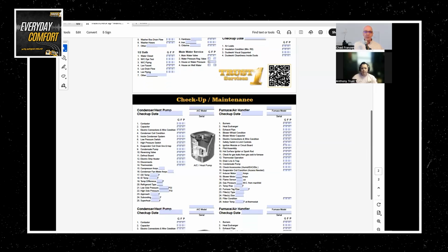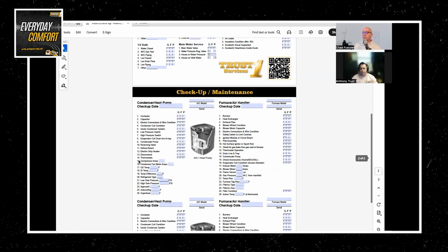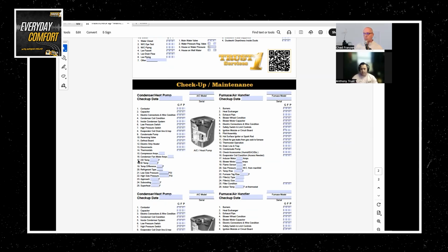You're checking capacitors, contactors, coils, refrigerant pressures, subcooling, superheat. Why is this level of detail important? Yeah. So like I said earlier in this episode, capacitors are basically the battery pack of the system when it comes to motors. If they have a good enough charge, it allows that motor to kick on. And a lot of these components are related to each other. Like a contactor, it transfers power from one side to the other when it has a call for AC. So that pulls in when there's power, it allows power to transfer from one side to the other. All these components are related to each other, making sure that the system has proper pressures.